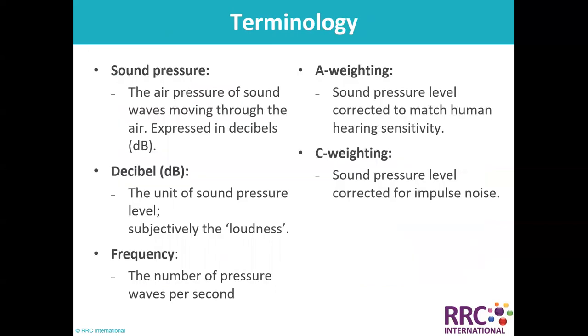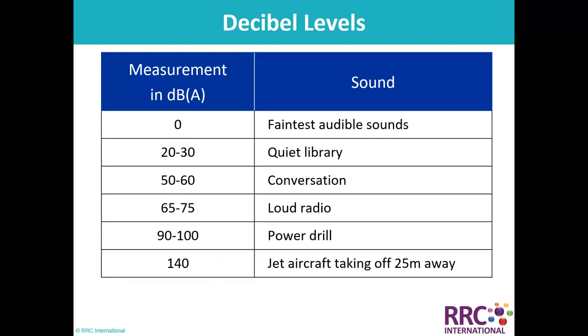Key terminology: sound pressure is the air pressure of sound waves moving through the air, expressed in decibels (dB). Frequency is the number of pressure waves per second. A-weighting corrects sound pressure level to match human hearing sensitivity; C-weighting corrects for impulse noise. Example decibel levels: faintest audible sounds 0 dB, quiet library 20–30 dB, conversation 50–60 dB, loud radio 65–75 dB, power drill 90–100 dB, jet aircraft taking off at 25 meters 140 dB.